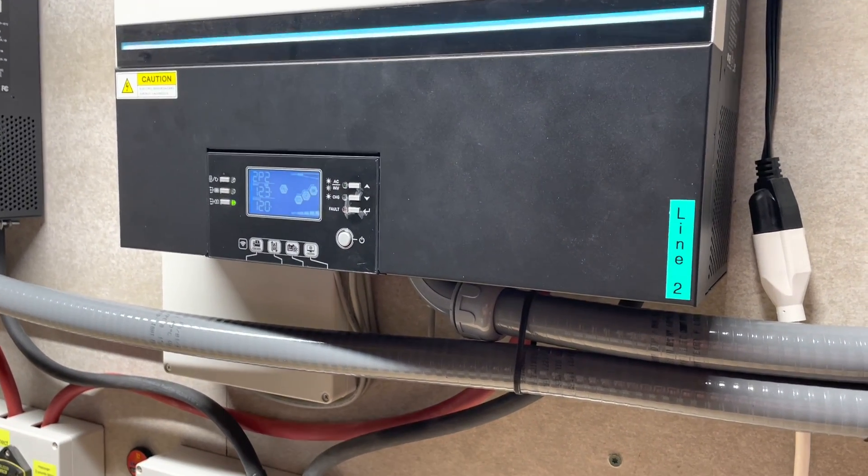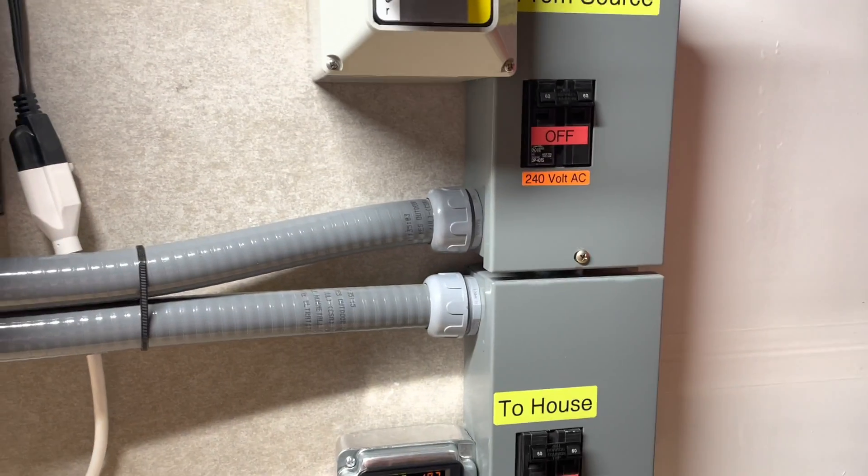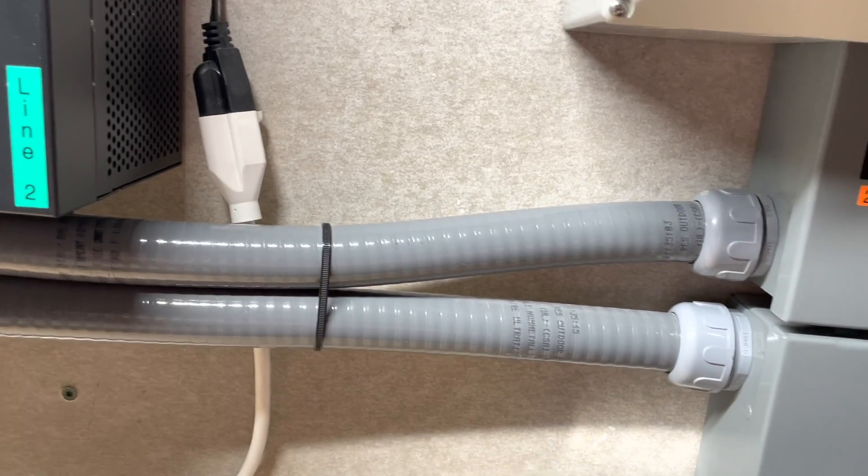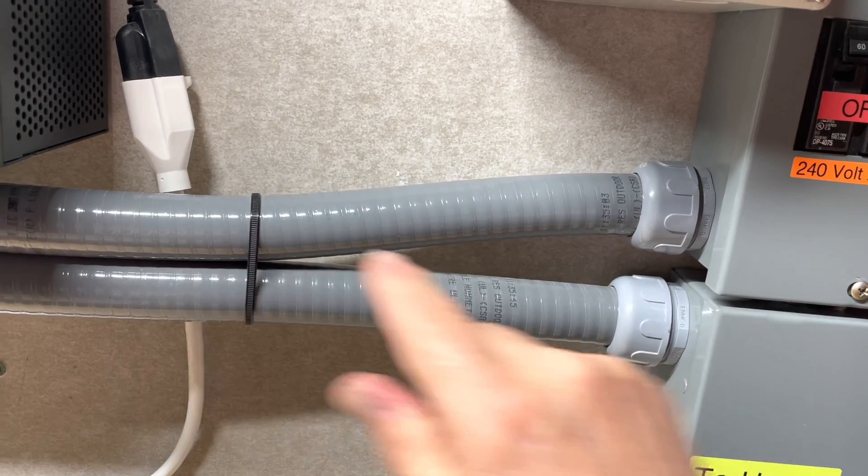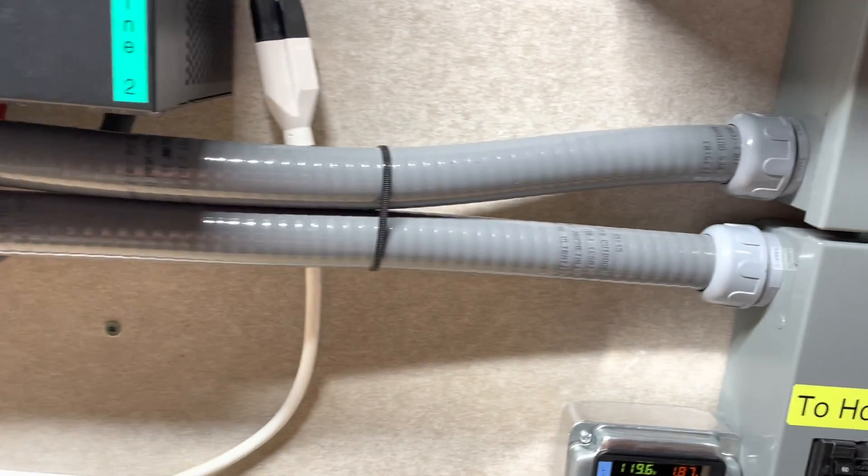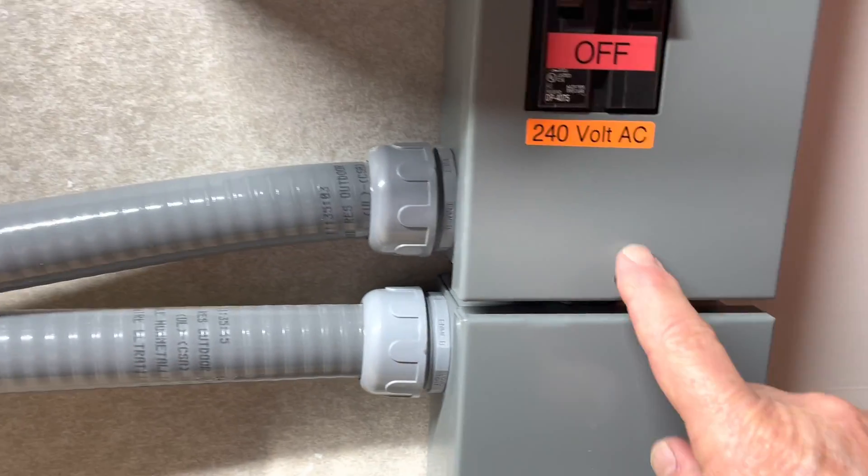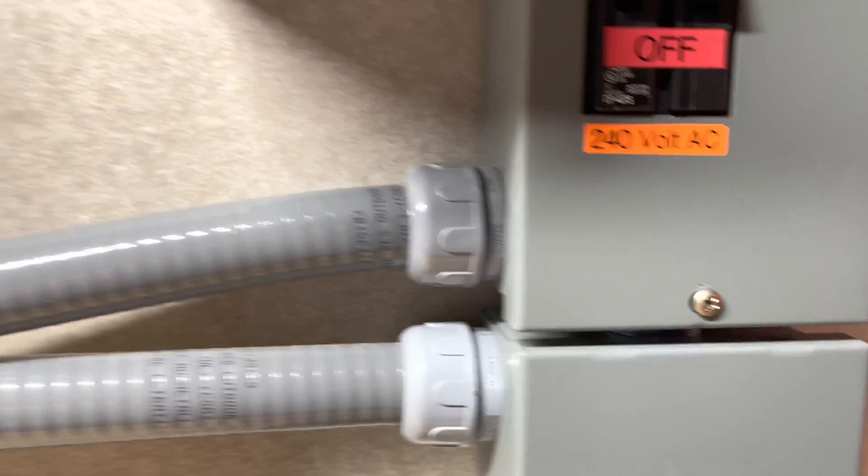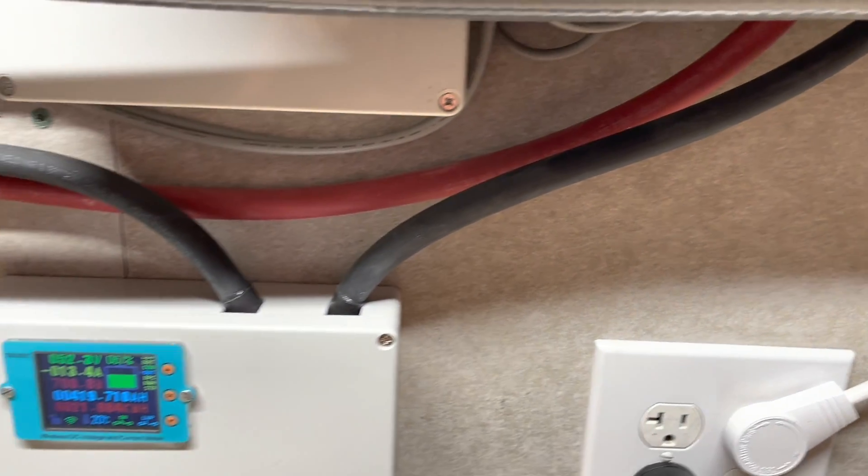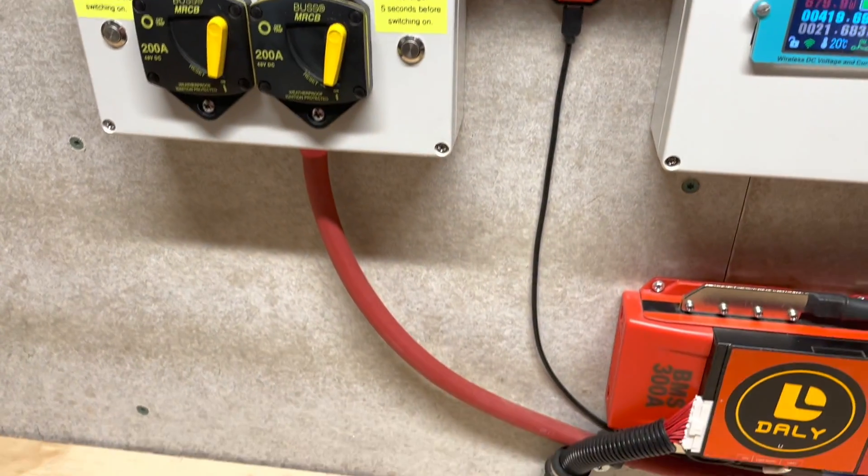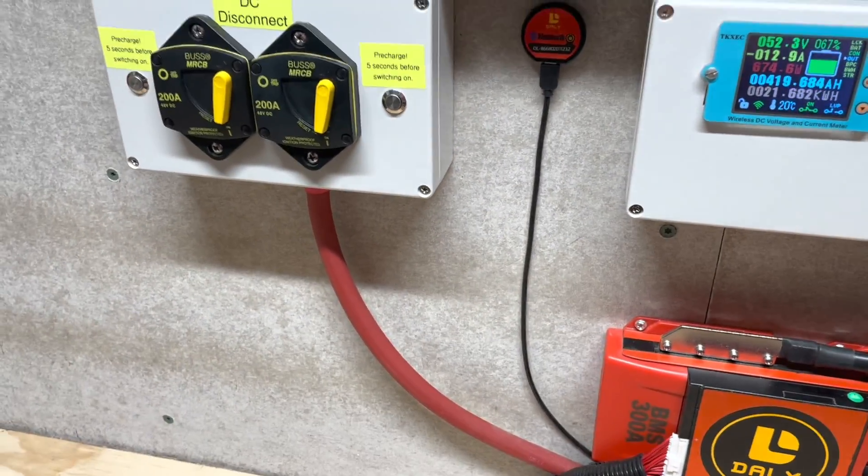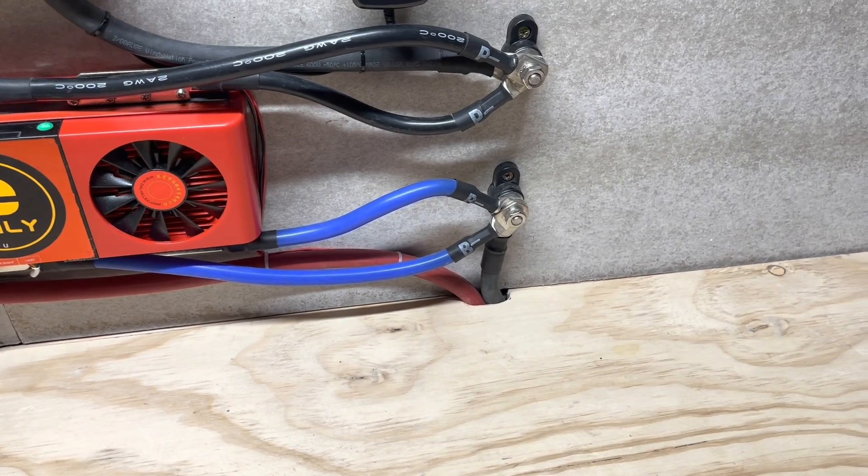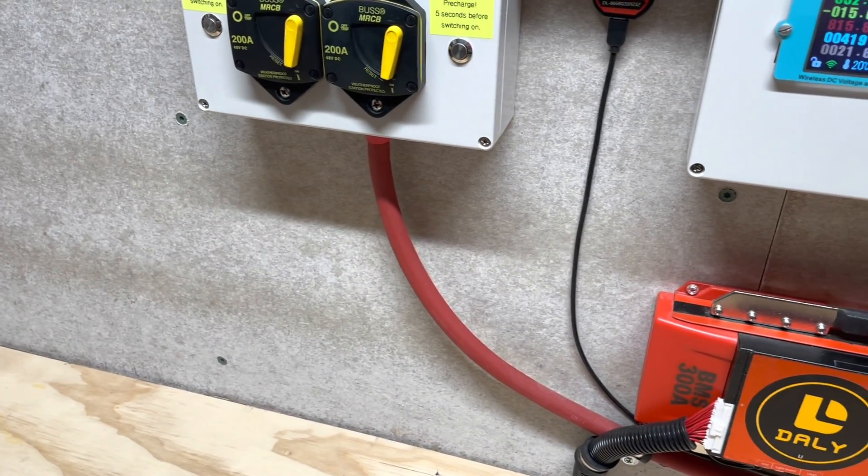The way this is wired looks a little confusing maybe with these conduits. Got some of these wires running from here that way to get to one, and some of these wires running from here to here and also from here to here going in. So I didn't have to run two conduits to each unit - it's sharing input lines and output lines in the same conduit, and then they just kind of cross between the units with a big nipple in between running pretty nicely there. That's 2-ought cable going down to the batteries. They only start to get a little warm once you get a little over 160 amps. Then yeah, it starts getting a little warm. You can feel some warmth coming off of it on a cold day.